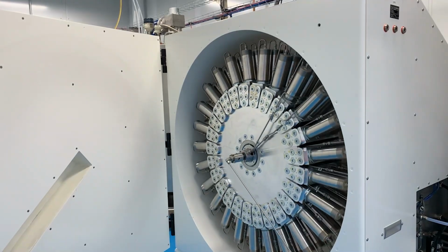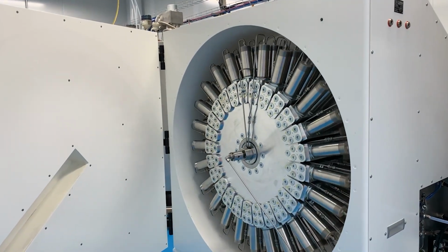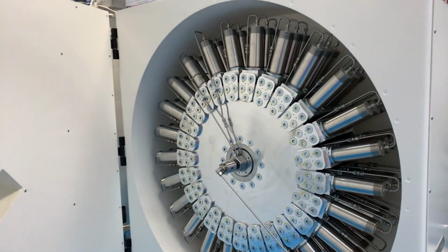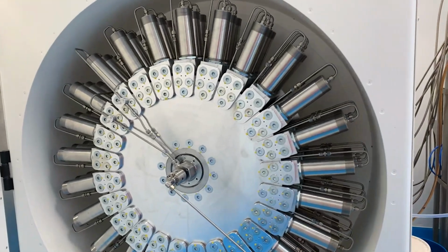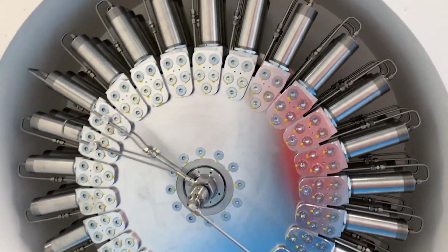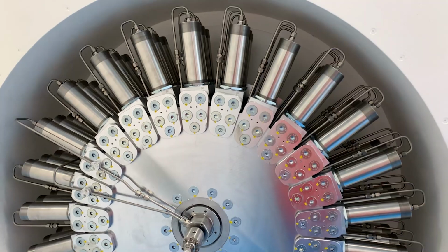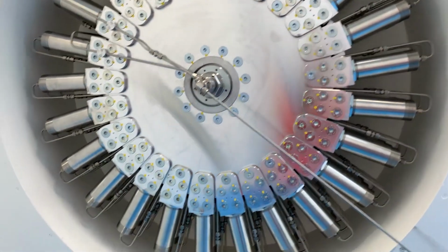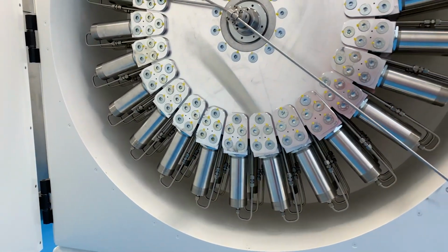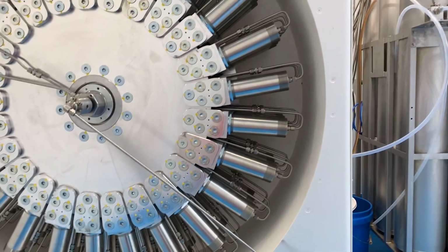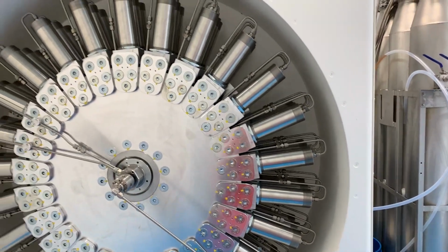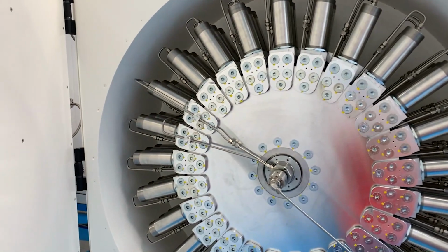This is the part of the system, the ICPC and the rotor. The column equivalent is 33 feet. As you can see, there are 3 wheels behind each other, each with 25 cells. They are interconnected, forming that 33 feet tall column. This is controlled by the control cabinet outside and is able to separate 9 fractions.